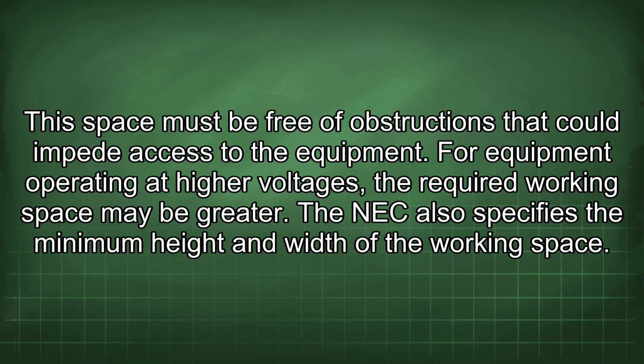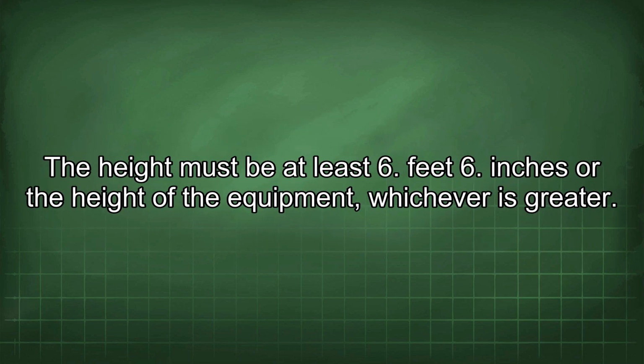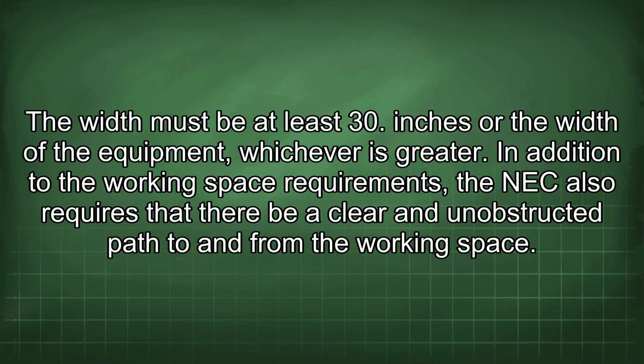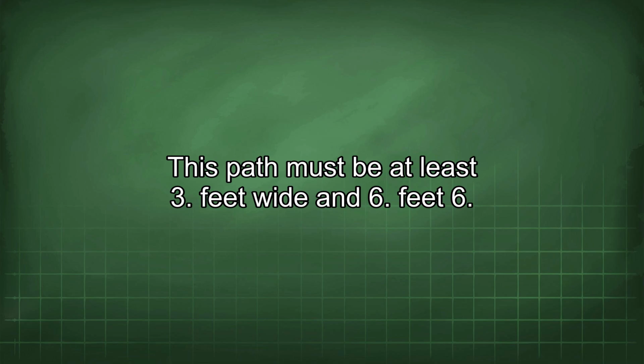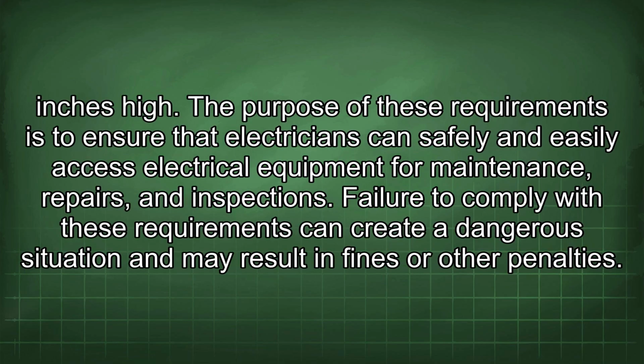The NEC also specifies the minimum height and width of the working space. The height must be at least 6 feet 6 inches or the height of the equipment, whichever is greater. The width must be at least 30 inches or the width of the equipment, whichever is greater. In addition to the working space requirements, the NEC also requires that there be a clear and unobstructed path to and from the working space. This path must be at least 3 feet wide and 6 feet 6 inches high.